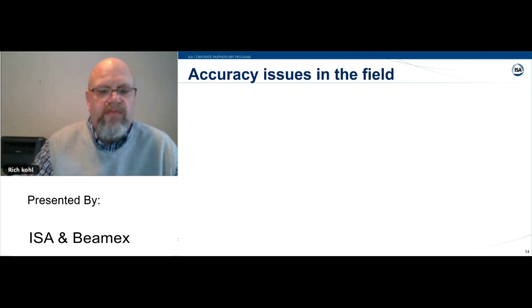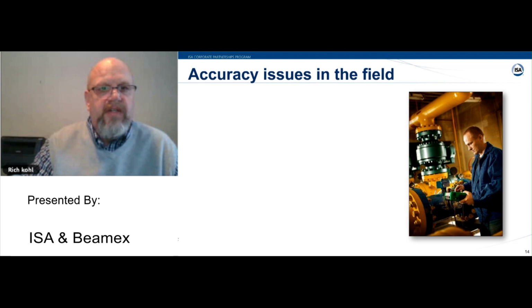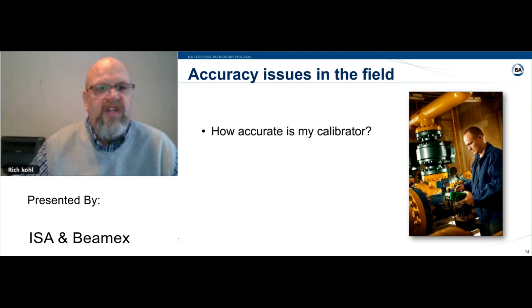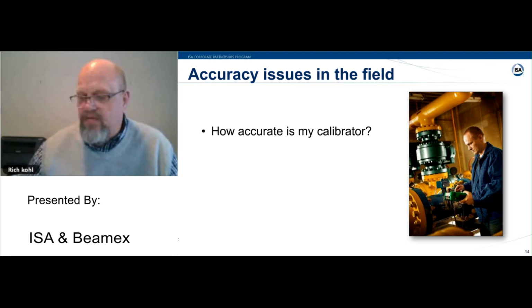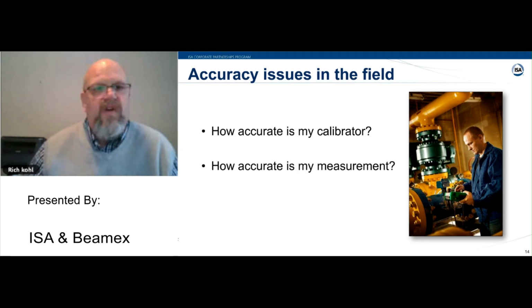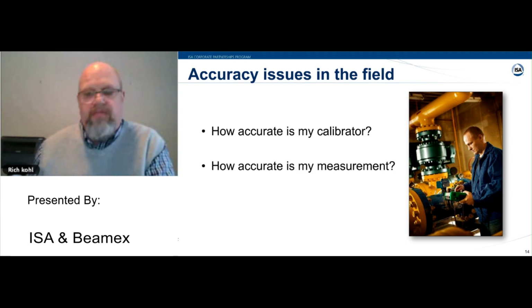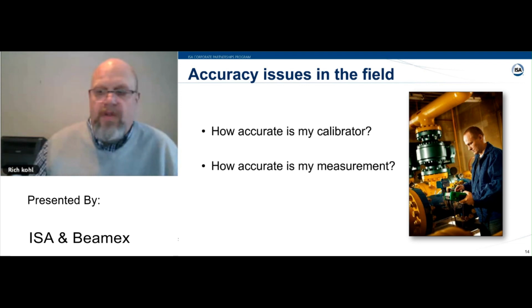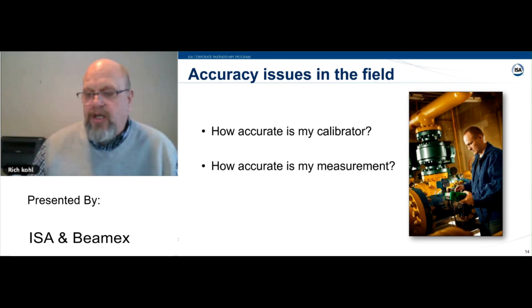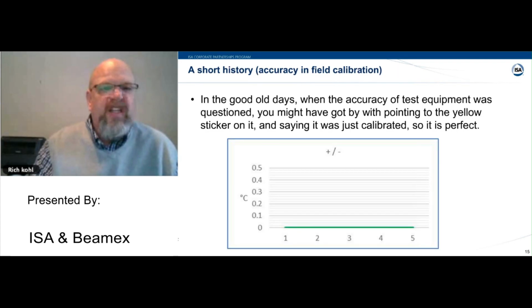So let's talk a little bit about calibrations in the field and the history of this. What we're going to talk about here is how accurate is my calibrator, and how accurate is my measurement. There is a difference between the two. Sometimes it's a big difference. The big takeaway from this section should be that the accuracy spec of the M&TE is only a part of the larger overall measurement accuracy. With that, we'll go on to the next slide.